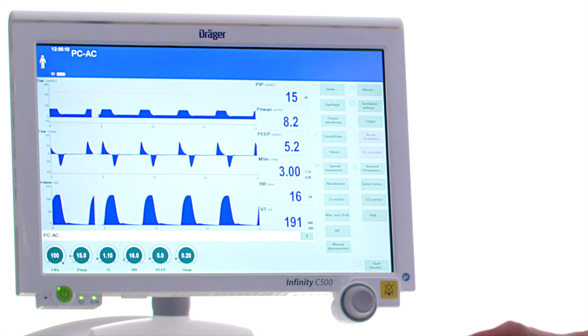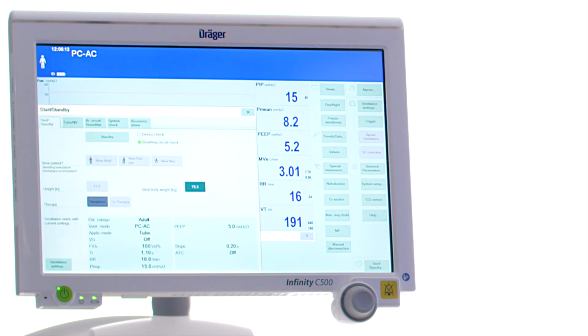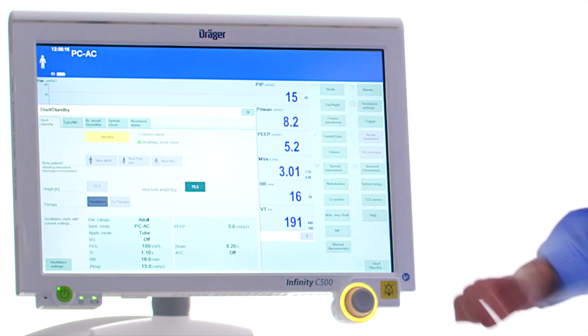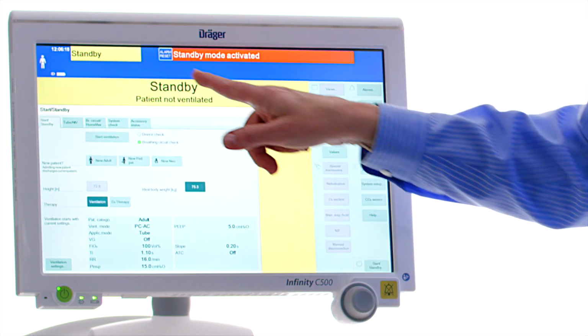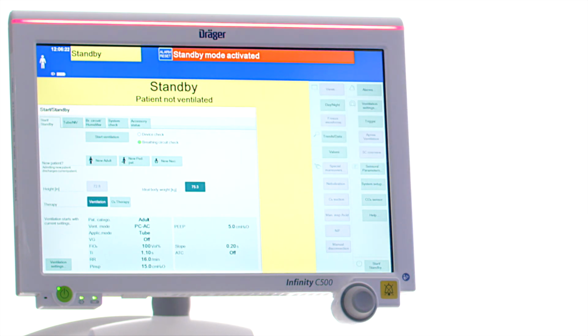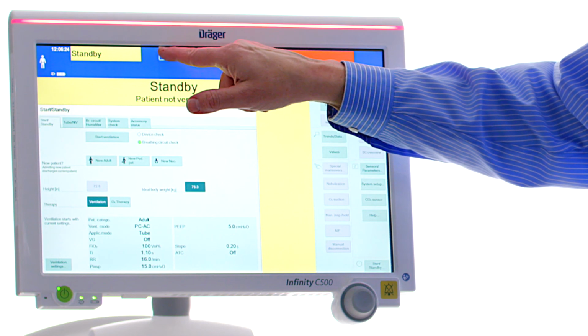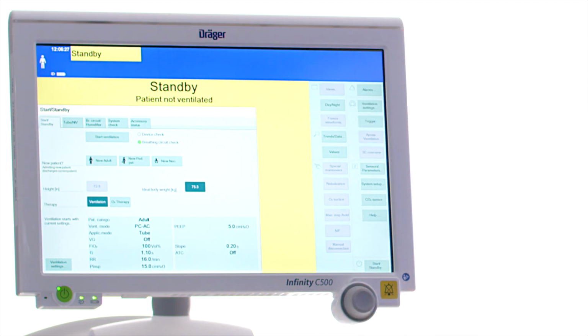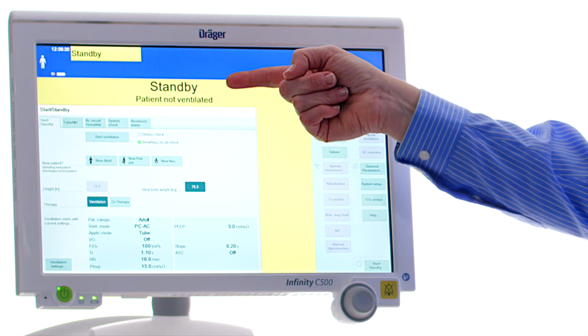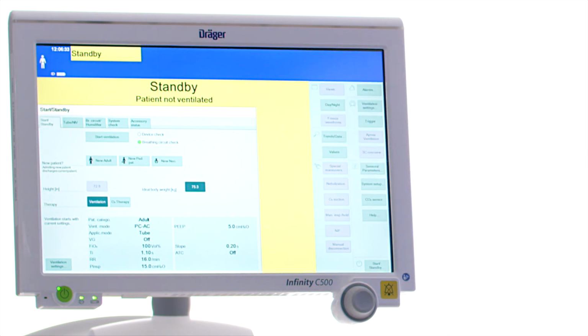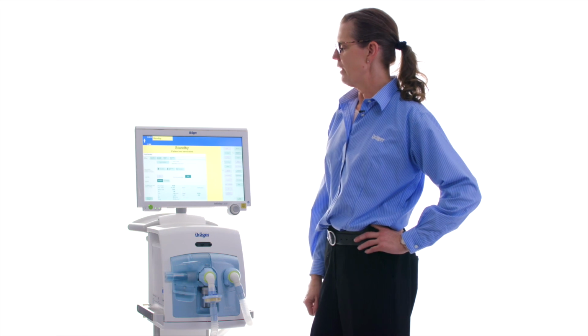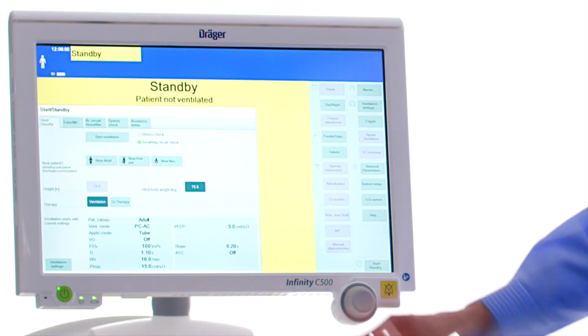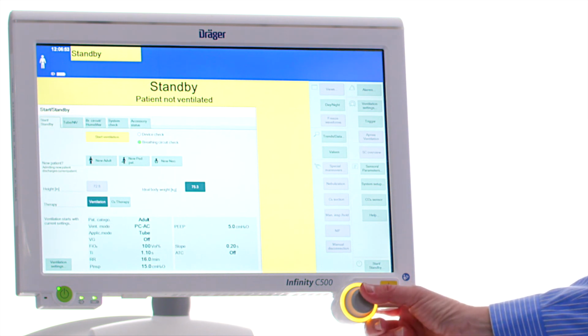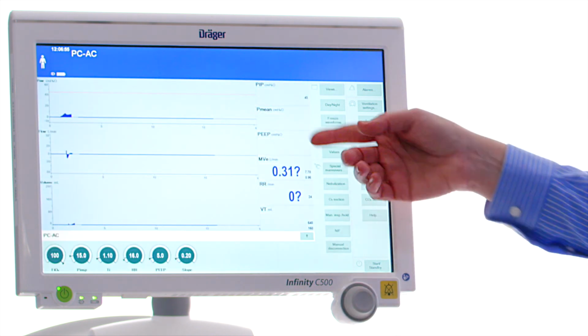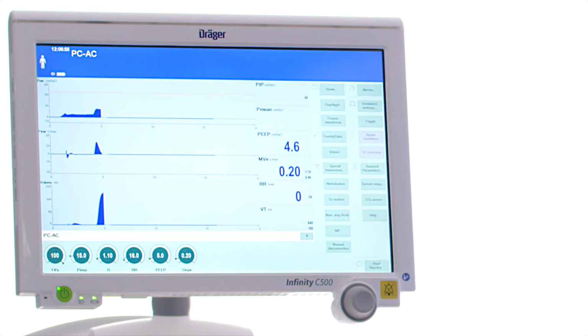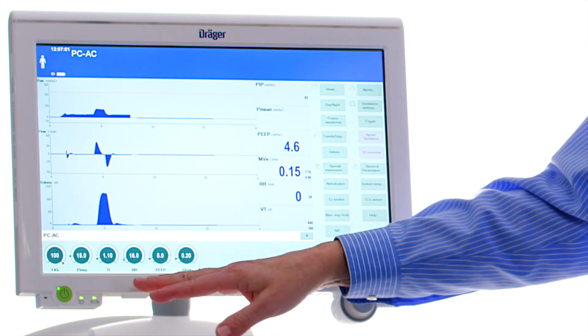To stop ventilation, you simply touch the Start Standby in the lower right-hand corner of the screen. Touch the standby button, confirm by pressing the rotary knob. The ventilator will indicate that your patient is no longer being ventilated and will alarm, which requires you to touch the alarm reset and confirm. The ventilator clearly indicates that the patient is not being ventilated at this time. The power button is in the lower left-hand corner. To restart ventilation, simply touch the Start Ventilation tab and confirm by pressing the rotary knob. And you'll be back ventilating at your previous settings and ventilator mode, measured values, set values.